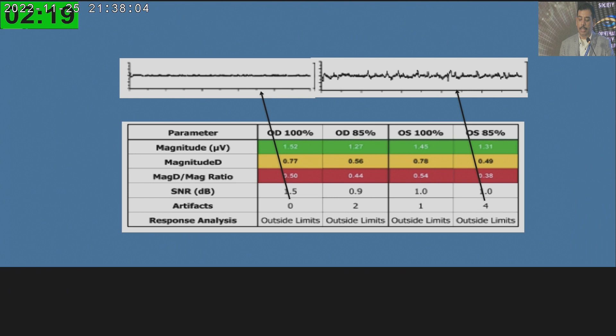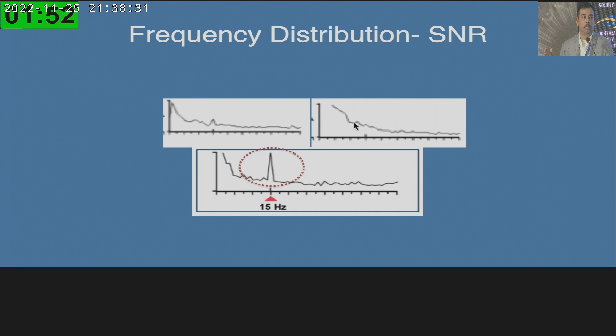Then the next area is the signal to noise ratio, which is the frequency distribution curve. You see there is a zone which I have marked at 15 hertz. 15 hertz is critical. You see that upshoot. If you don't see that upshoot, and the deviation is more towards the right side, where the signal to noise ratio is pretty low, then again these charts are not to be considered.